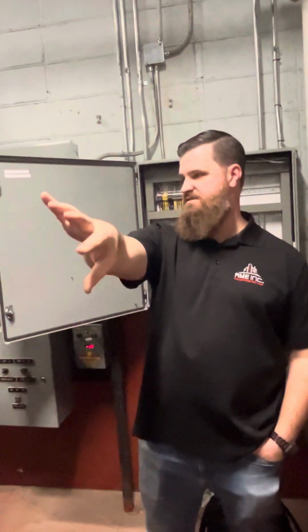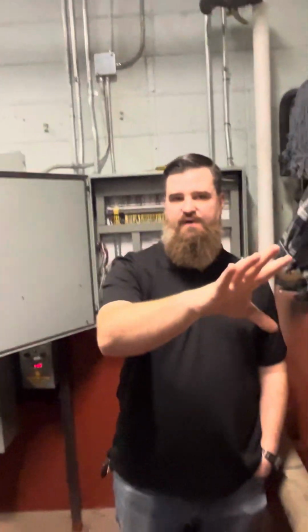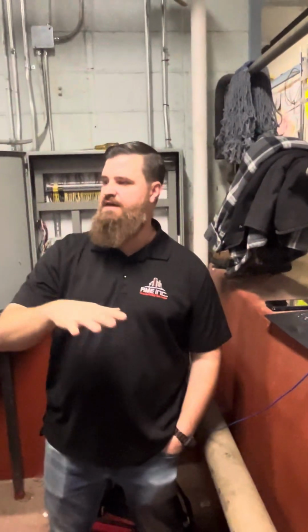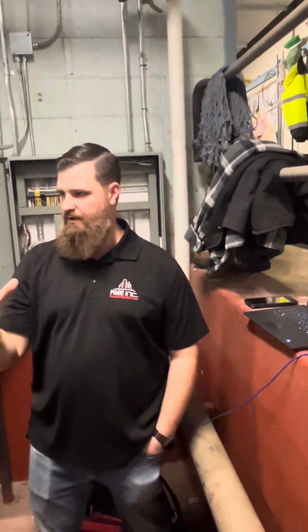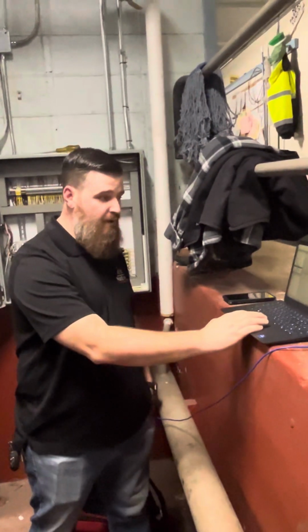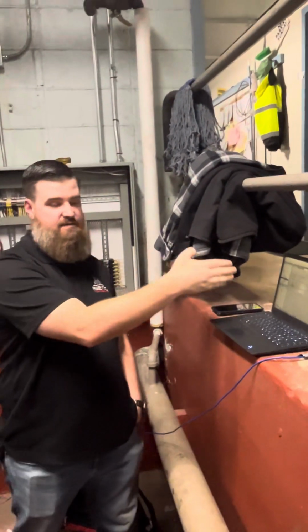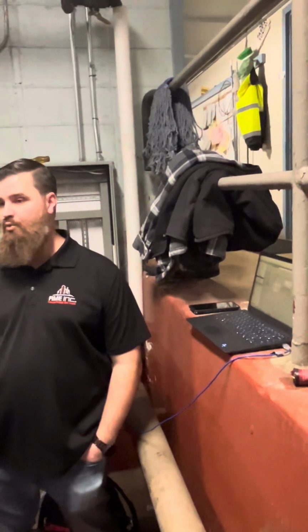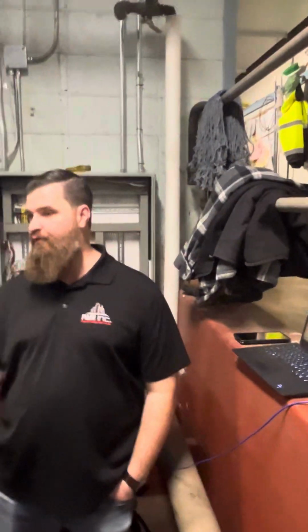Okay, on the boilers themselves. So basically, we want to be able to just turn the boilers off, and then whatever the boilers have is sort of like a high limit, just to prevent them from going too high. Okay. But again, I also need it so that if you guys say, hey, it's really, really cold, we need to go to 4 pounds, I need to be able to hit 4 pounds. Now, if I hit 4 pounds and he's only set for 4, well, we're always going to be sitting at 4, and we're going to be firing all 3 boilers to maintain 4. But if we need all 3 boilers to maintain 4, you're using a lot of steam out there.